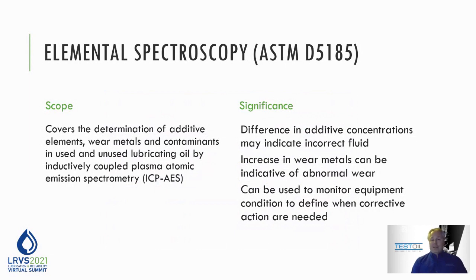But ultimately, we're barely scratching the surface at additive presence, because essentially with this test, all we're doing is confirming that the building blocks of the additives are present, and therefore the assumption is it's just the right oil. And that's about as far as we can take the interpretation of additives being measured by elemental spectroscopy. But allow me to explain further, and you'll come to understand what I mean by this.